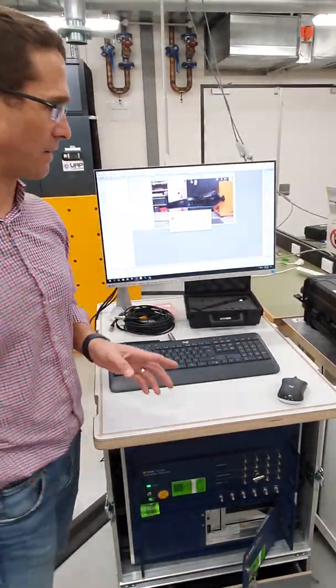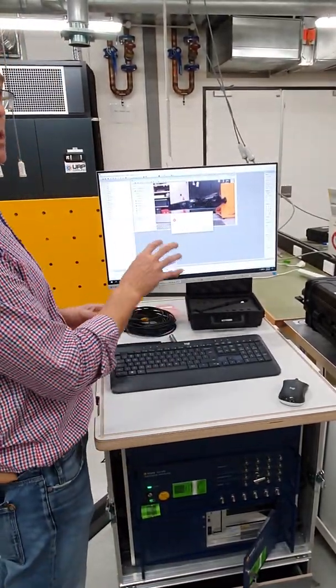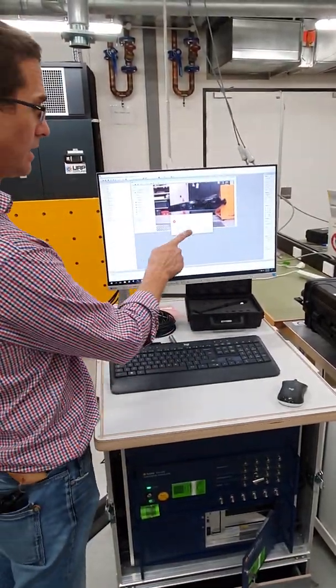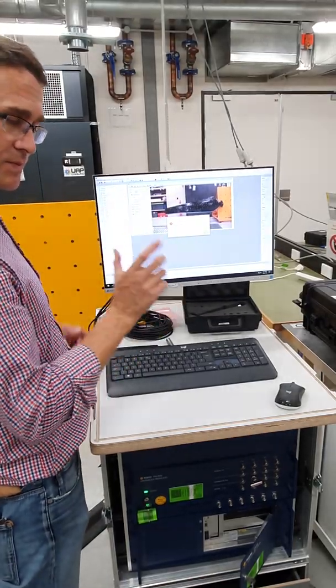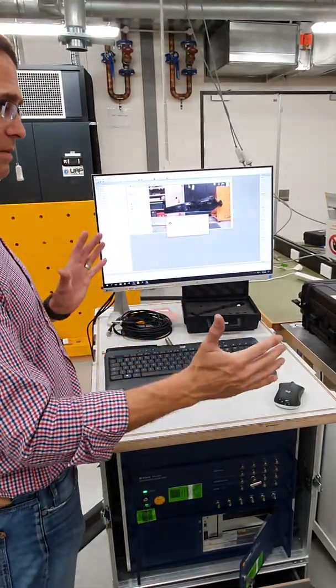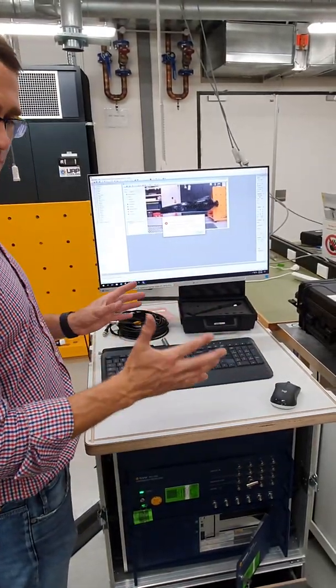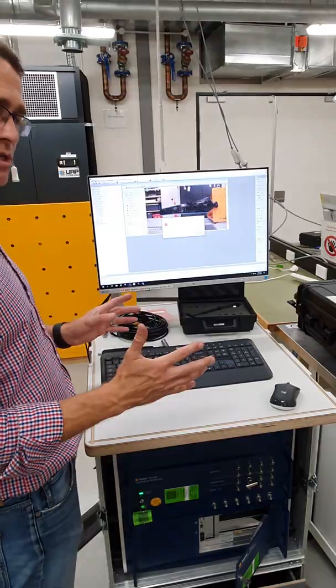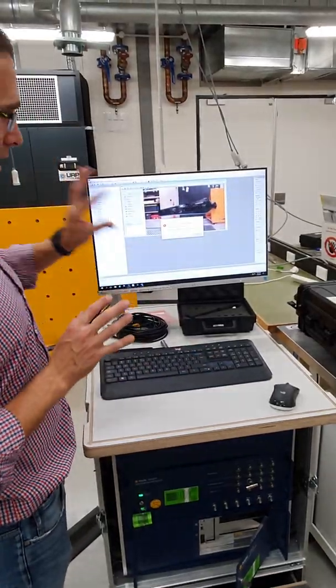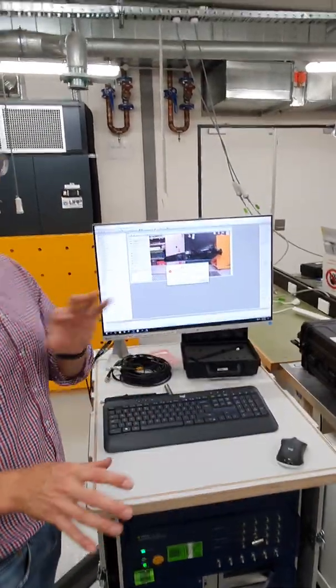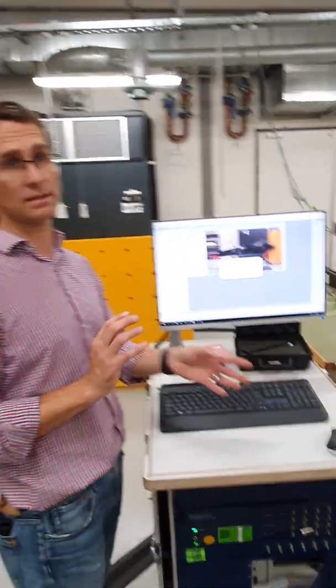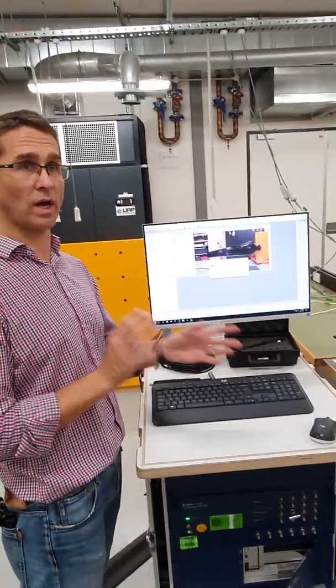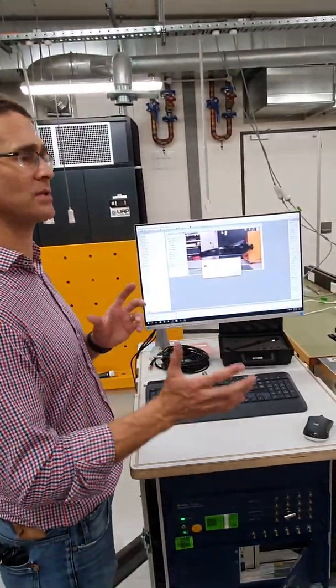And when we change the scanning heads between the controller, same cable and everything, the software changes because the maximum dynamic range changes in the controller depending on which scanning head we have connected. Because we've got different wavelengths of light there, we have different vibrometers.